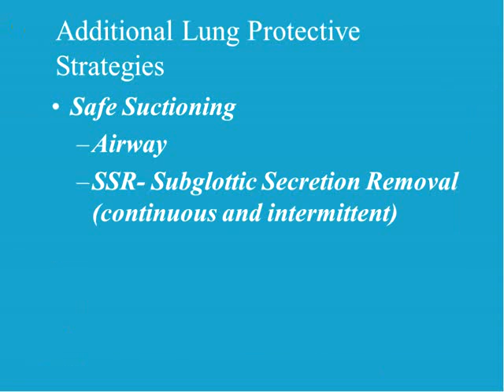The AARC released new clinical practice guidelines regarding endotracheal suctioning in the June 2010 issue of Respiratory Care. The highlights of that guideline are suction pressures: for adults, less than 150 millimeters of mercury; for neonatal and pediatric patients, less than 80 to 100 millimeters of mercury. Now, this doesn't say that if you're using 120 as your standard operating procedure, you should increase the pressure to 150. In fact, in all things suctioning, you should always use the minimal amount of pressure that's appropriate to achieve the goal you're trying to achieve.